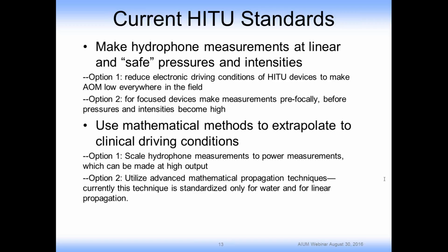The second option, where you made the prefocal measurements, can be supported by some advanced mathematical propagation techniques. It's essentially using techniques for solving partial differential equations to capture data that was taken in the prefocal plane and plug it into a partial differential equation type of solution that can predict what the pressure would be elsewhere in the field. And currently, this technique is standardized only for water and for linear propagation. That is, it does not include the nonlinearities that occur in water or potentially in tissue. But that is currently in the standards using these propagation techniques.